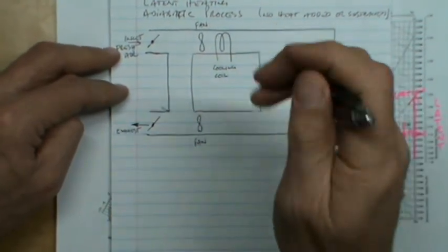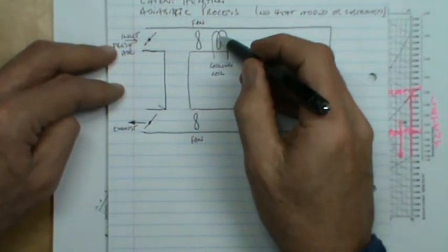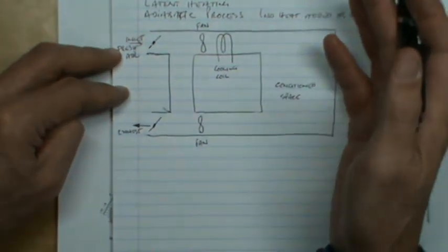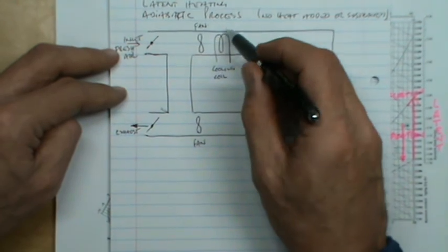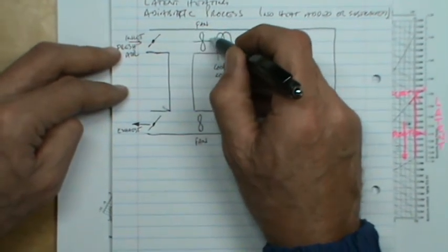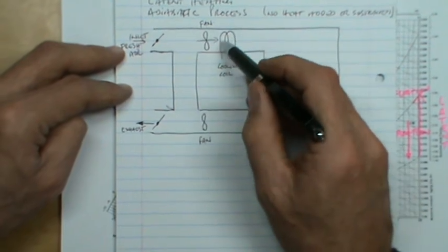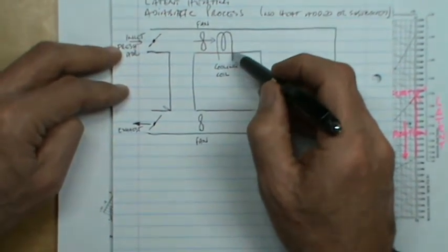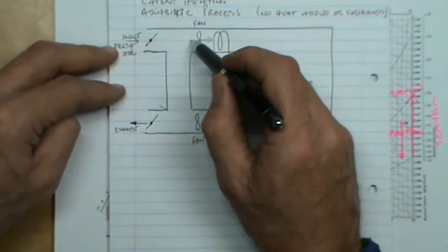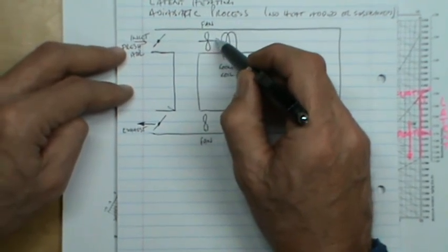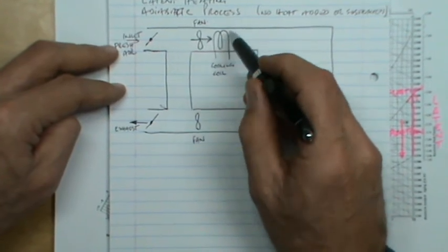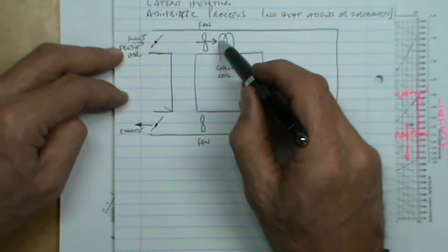But whatever happens in that particular case, if it's direct injection or if it's not direct injection, whatever air is now flowing in this direction flows through that cooling coil. And what happens is that the heat that is in the air, as well as the moisture that is in the air over here, will now be treated as it comes through this coil.